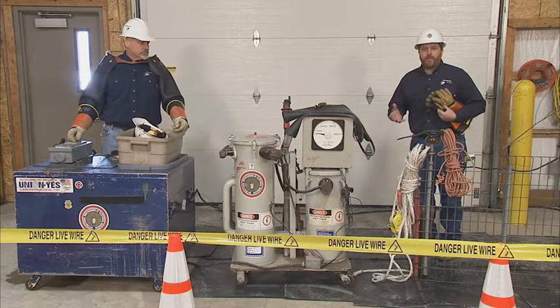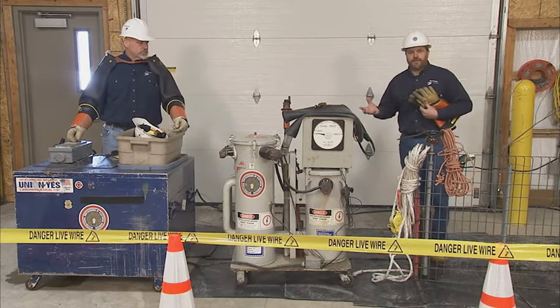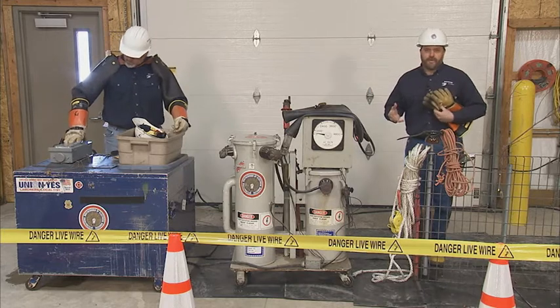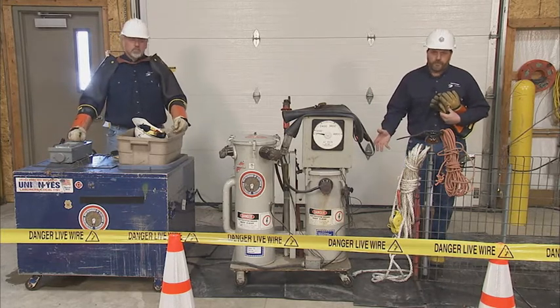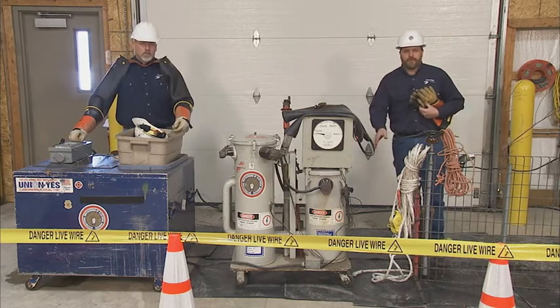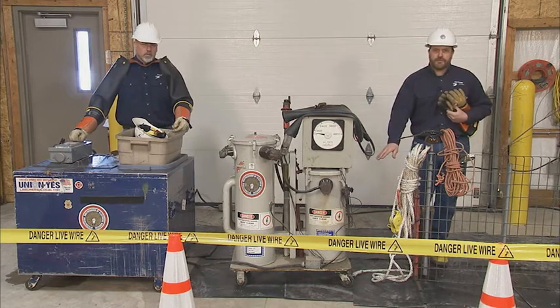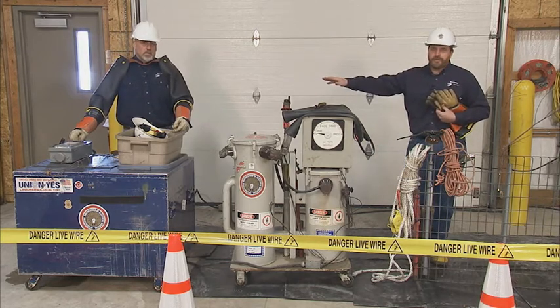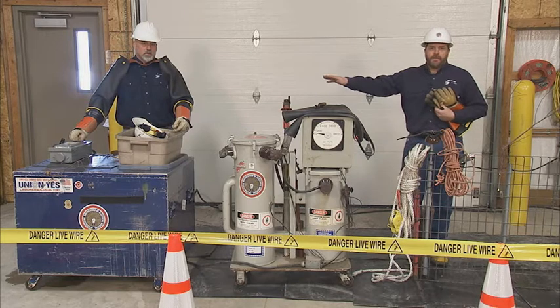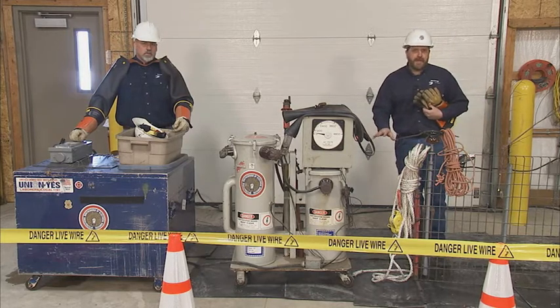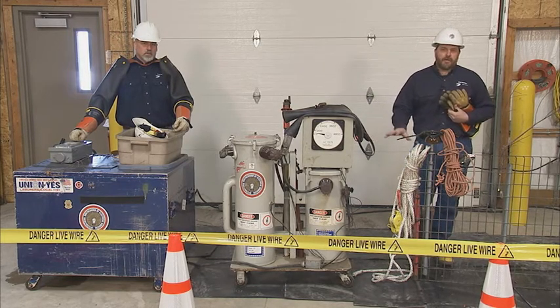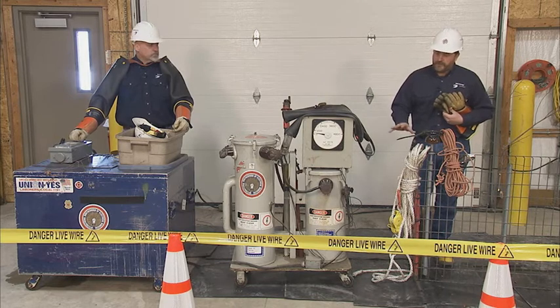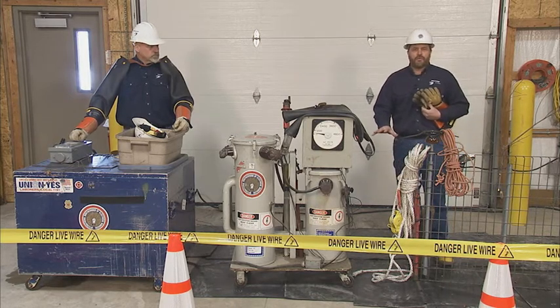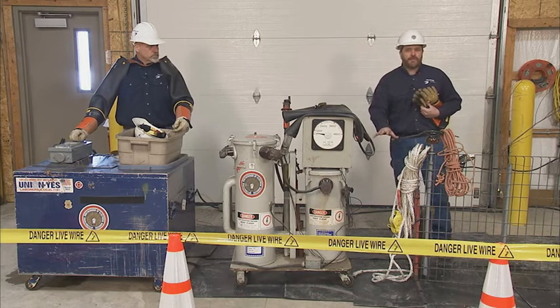You probably wonder how we're going to be able to produce such a high voltage in a small arena here. We're taking a transformer and taking 120 and 240 volts on the secondary side of the transformer, and we're going to be able to produce 4,800 volts on the top side. What we're doing essentially is backfeeding this transformer. We like to talk about this especially because this is what could happen during one of our storms or a normal day-to-day operation out there.